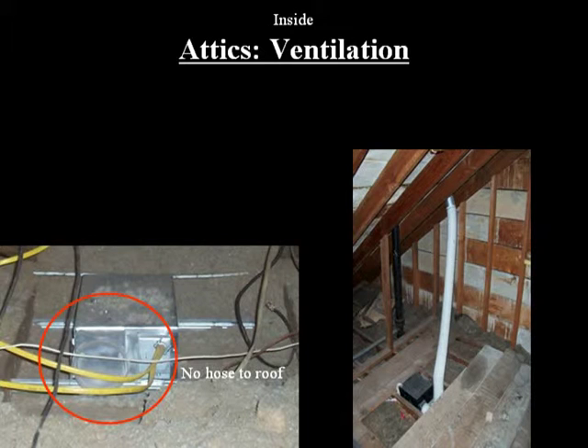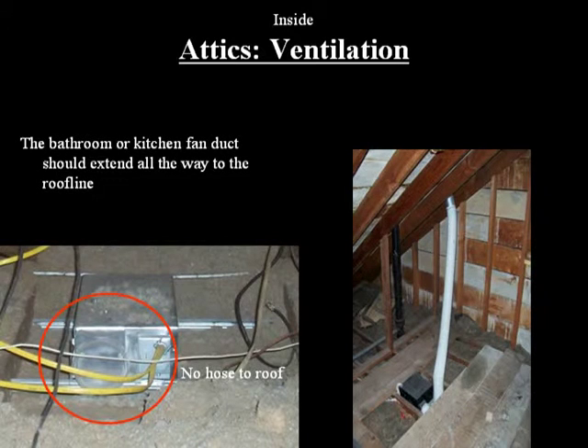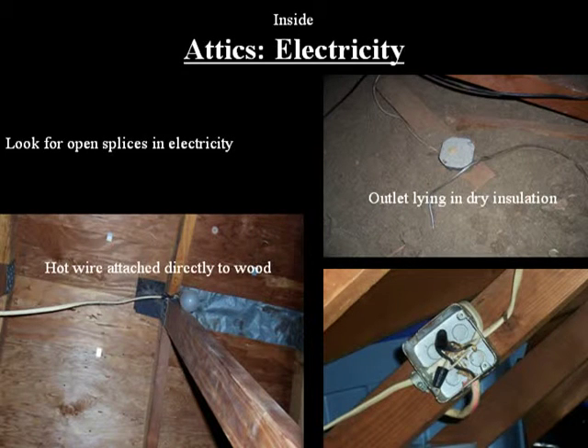Bathroom fans discharge directly into the attic more often than they should. When you use the bathroom fan, moisturized air flows up into the attic and condenses, which leads us to problems. The fan duct should extend all the way to the roof line and discharge into the atmosphere. Take a quick look for open splices in electricity, just like in the garage. Make sure any receptacles present are definitely covered.